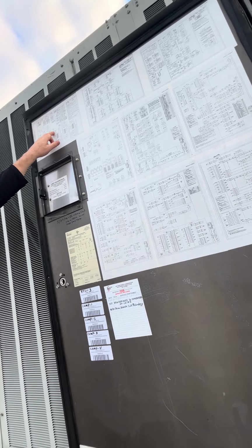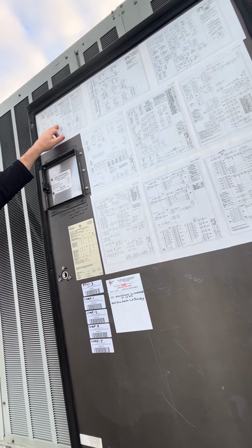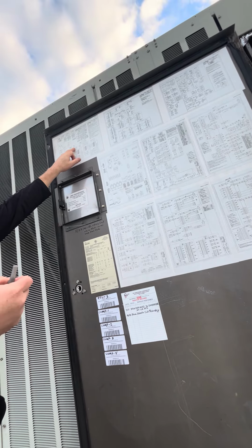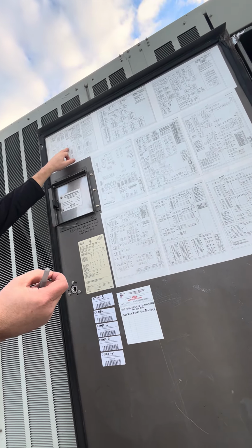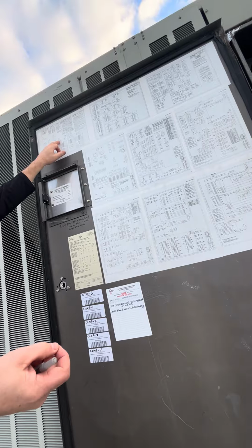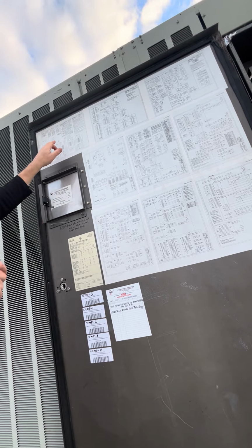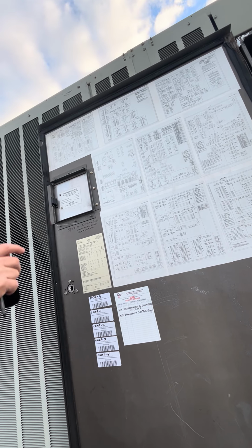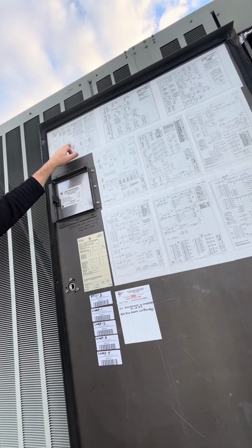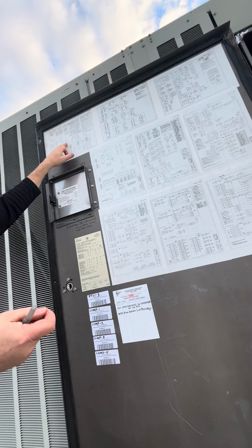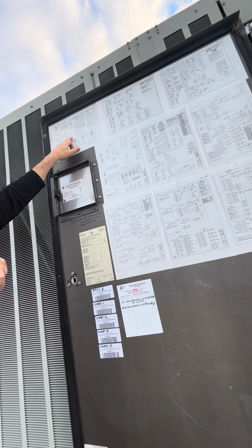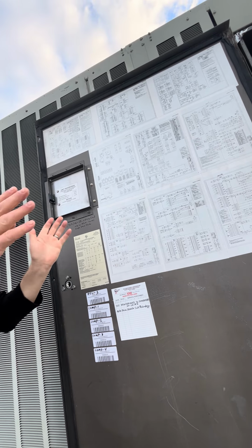And you can program it as 0%, meaning you can lock out 0% of the cooling. You can lock out 50% of the cooling, or you can lock out 100% of the cooling. We don't use this for that utility demand limit strategy, but we use it as a mechanical cooling lockout. So we set it up for 100%. When we give this a closure, the unit can't run cooling.